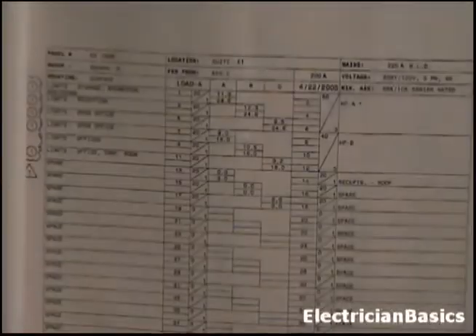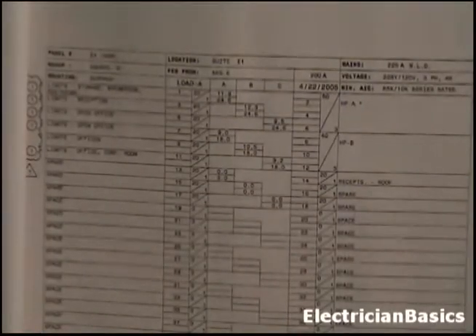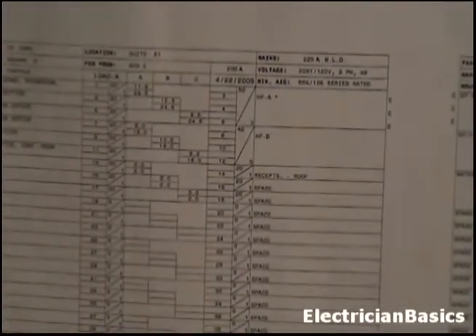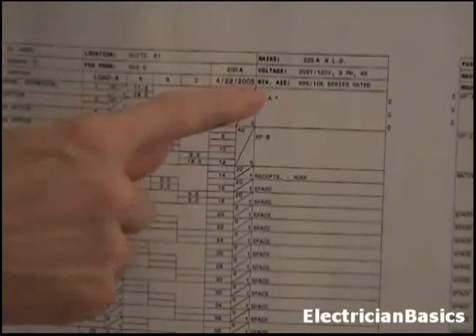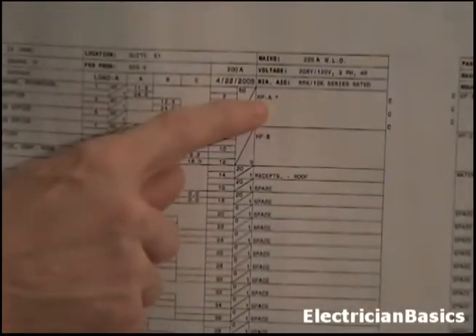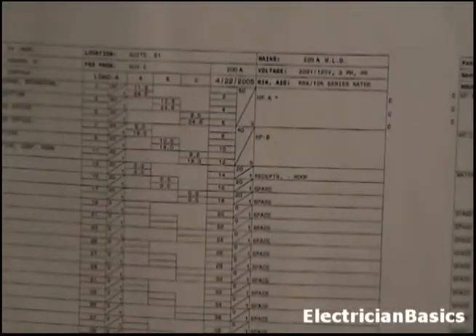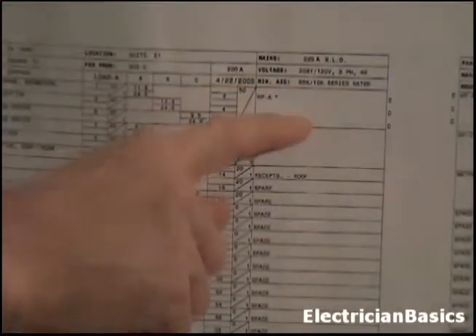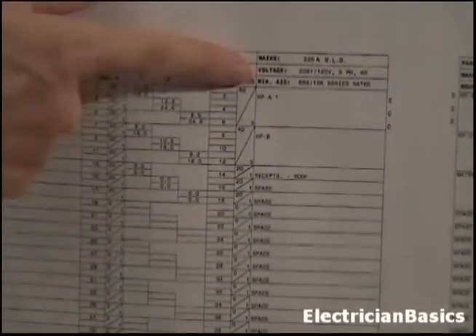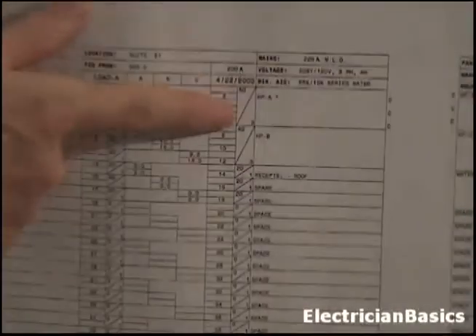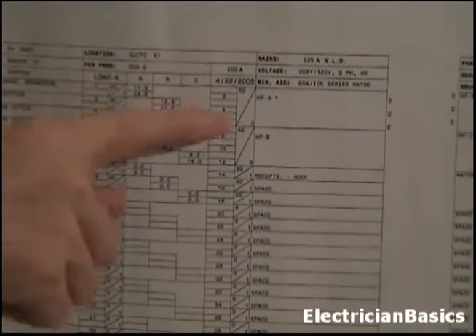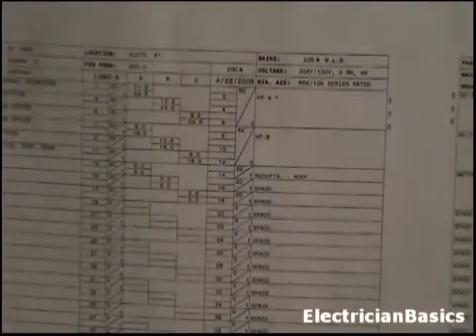Let's go over to the other side of the panel and let's look at the even numbered circuits. Okay. So I just want to bring our diagram this way a little bit. We have here, it's HPA. Now that's heat pump A, and we know that's roof mounted. And look, it's got this whole section. We see how this is broken up over here. Well, if you look at this line, this diagonal line that comes through, and then it's got 3. That means it's a 3-pole breaker. So it's going to take all 3 of these circuits to power heat pump A. And it's going to be a 50 amp breaker. It's going to be circuits 2, 4, and 6.